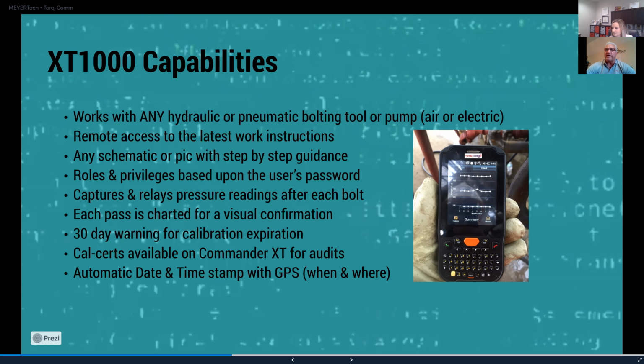You get a 30-day warning for calibration expiration, because we monitor our tools not just by make and model, but by serial number. So it gives the operator a 30-day warning, and if they don't get that tool recalibrated, it will not allow them to continue using it. The only way to override that is for a supervisor to come and input his 4-digit PIN code authorizing the use of that out-of-calibration tool. However, that goes into the final report, it will say the supervisor authorized the use of this tool. Calibration certificates can be made available on the commander for auditing purposes, and you get an automatic date and time stamp with a GPS stamp, so you'll always know when and where on earth the job occurred.